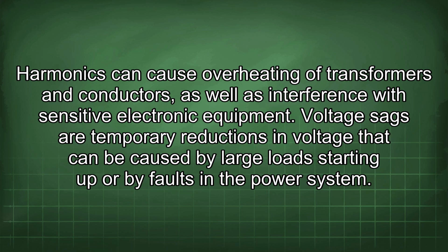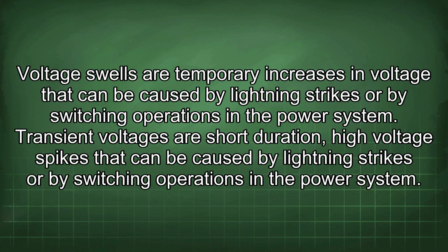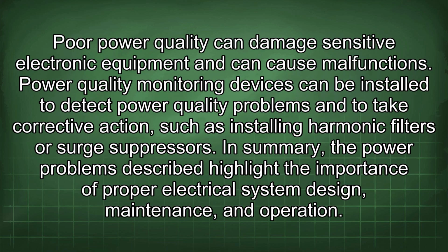Voltage sags are temporary reductions in voltage that can be caused by large loads starting up or by faults in the power system. Voltage swells are temporary increases in voltage that can be caused by lightning strikes or by switching operations in the power system. Transient voltages are short-duration high-voltage spikes that can be caused by lightning strikes or by switching operations in the power system. Poor power quality can damage sensitive electronic equipment and can cause malfunctions. Power quality monitoring devices can be installed to detect power quality problems and to take corrective action, such as installing harmonic filters or surge suppressors.